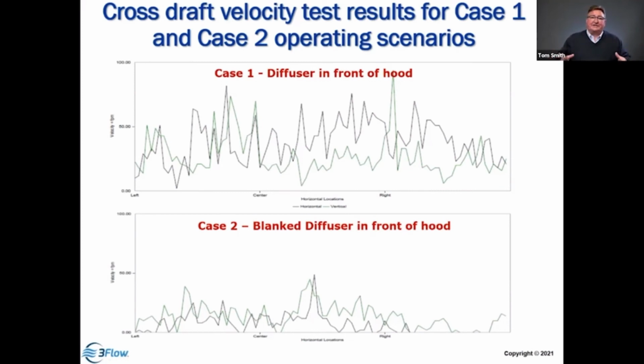But if it's excessive, it's going to cause flow fluctuations, perturbations in flow that cause loss of containment and exposure to the operator. So by reducing the draft, we make space for enabling the hood to be more effective and potentially safer to protect the occupant. So reducing exhaust draft is very important. It also impacts average space velocity.